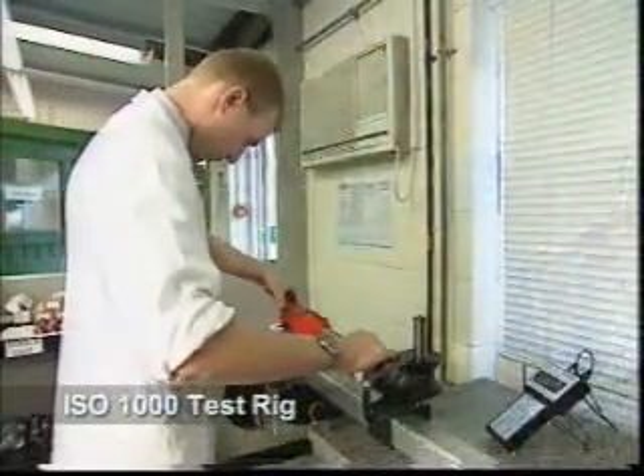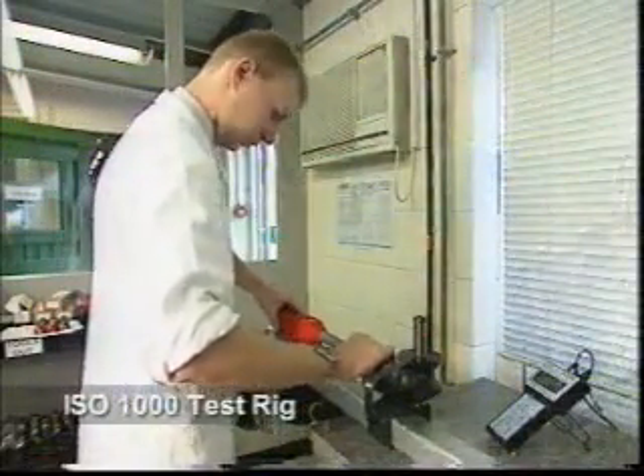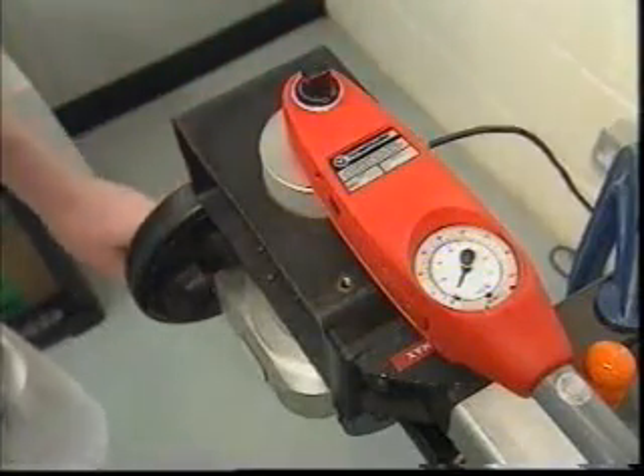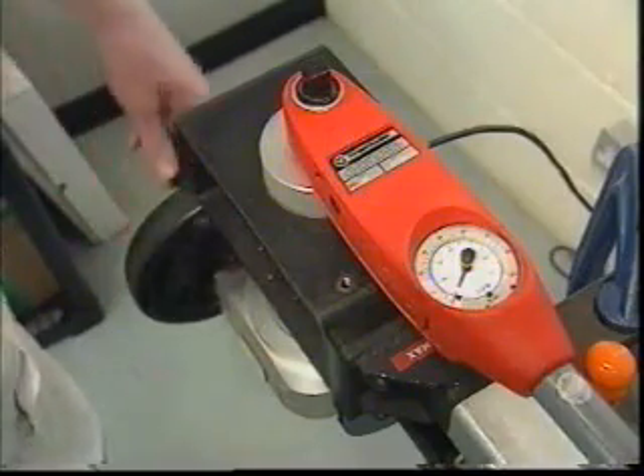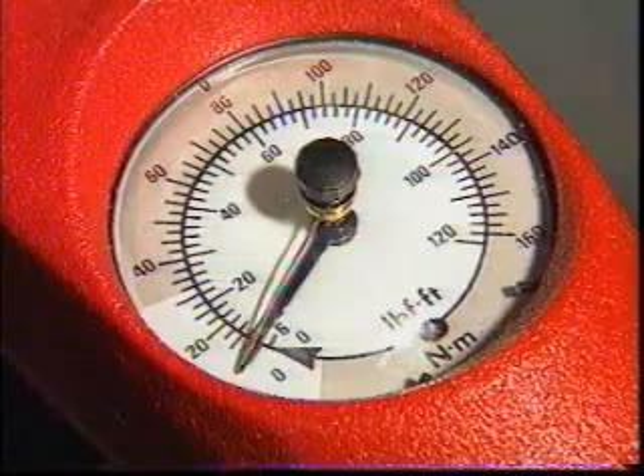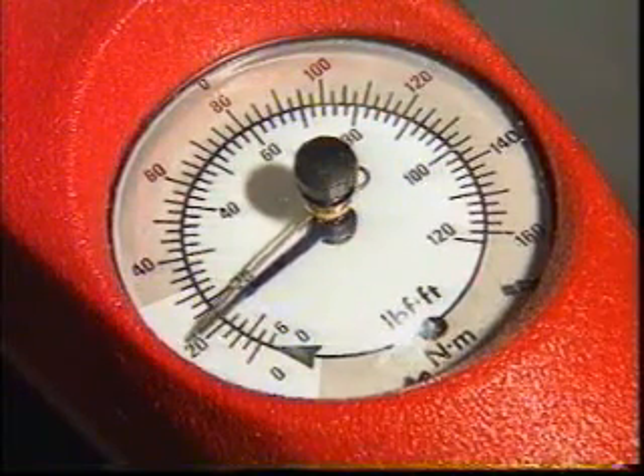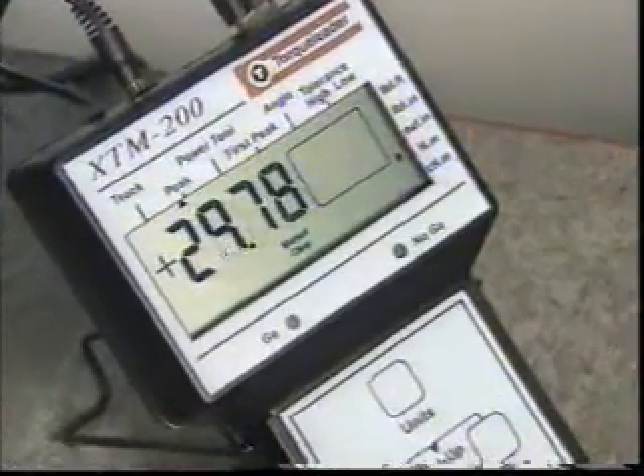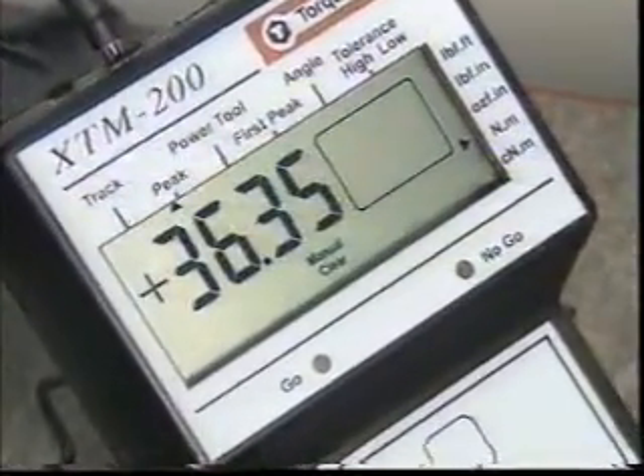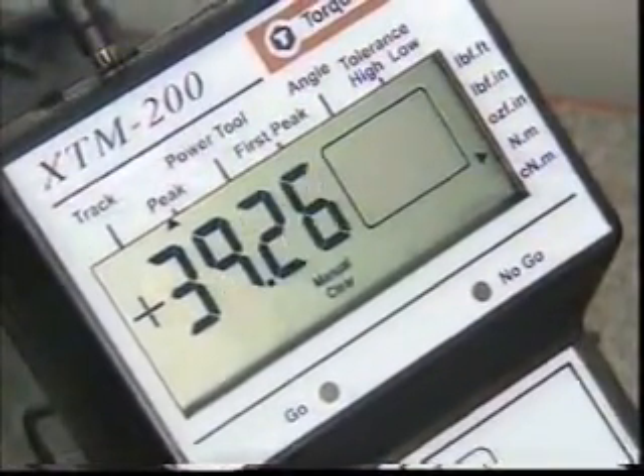The ISO 1000 test rig has been designed to verify the accuracy of torque wrenches to the stringent requirements of ISO 6789, the international standard for torque tools. Here we see the test rig in use with the XTM200 portable torque calibration analyzer.